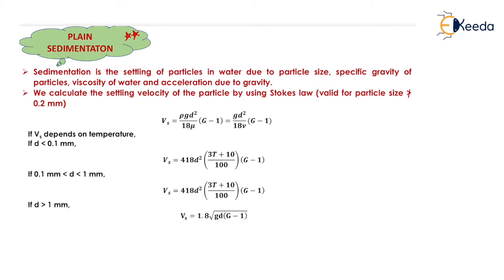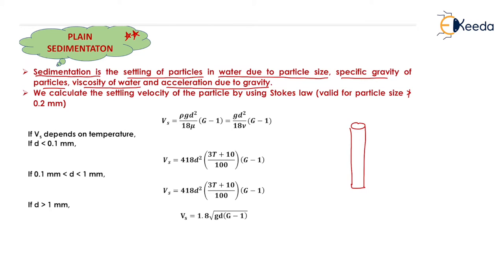In the plain sedimentation process, water is generally kept in a large container and allowed to settle under the influence of gravity by providing sufficient detention time. When the particles settle down, we remove them from the tank and send the water for the next process, which is sedimentation aided with coagulation and flocculation. Sedimentation is the settling of particles in water due to particle size, specific gravity of the particle, viscosity of water, and acceleration due to gravity.